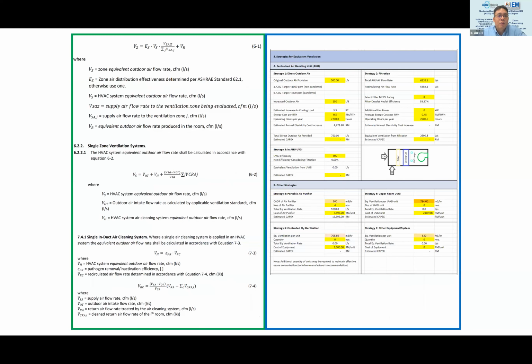Then of course there are a lot of formulas. The main difference is that the CIA, Control of Infectious Aerosol standard, basically follows the route of the air -- the AHU air goes to the space, then comes back as return air and is added with fresh air. When the air reaches the space, there's a portable air purifier, and you deduct this flow rate out. Designers will be very familiar with this.